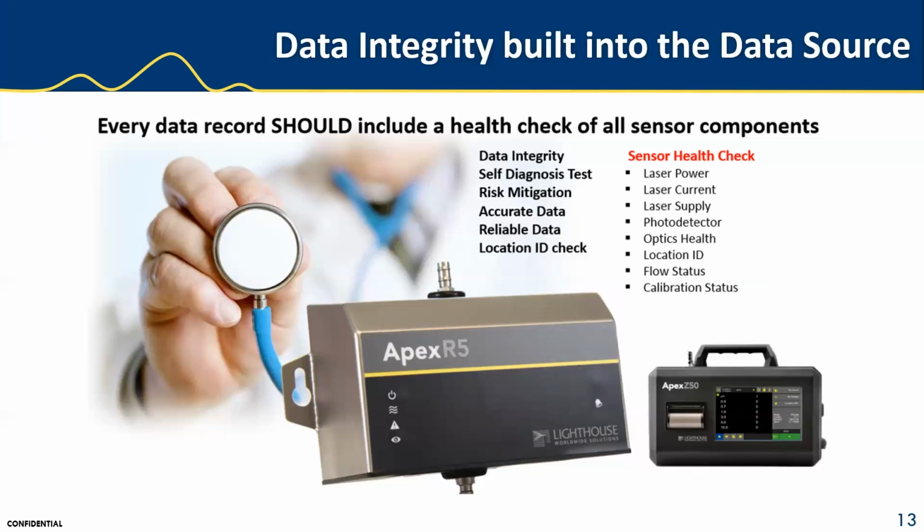Now, how about getting that data to its final destination? Well, we did cover this in detail in a previous webinar where we highlighted how we can digitally transfer that data to, say, a network printer or a secure file location on a network. All this without the need to even print the data from the particle counter. Speaking about that, did you know that thermal paper is not very environmentally friendly? The ink used is toxic, and the thermal paper cannot be recycled.